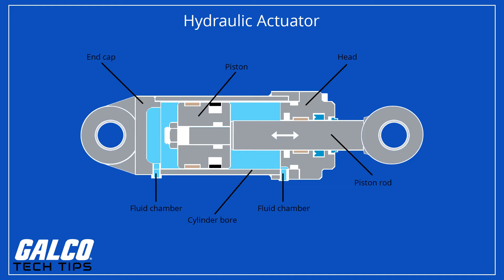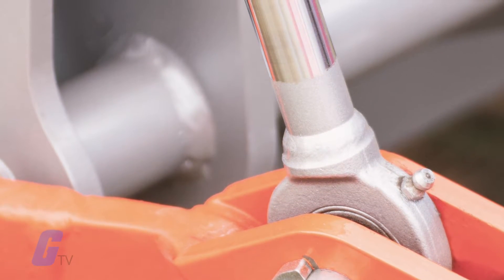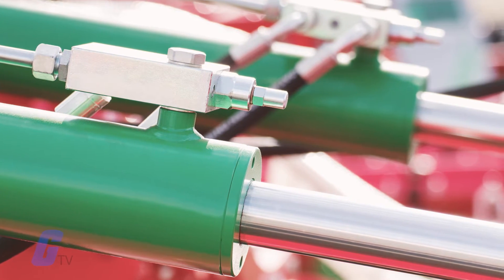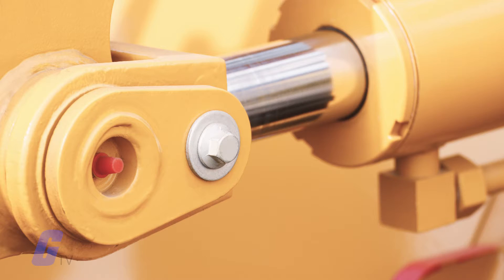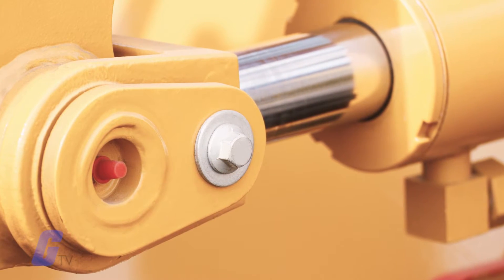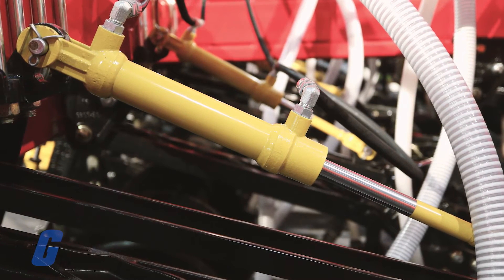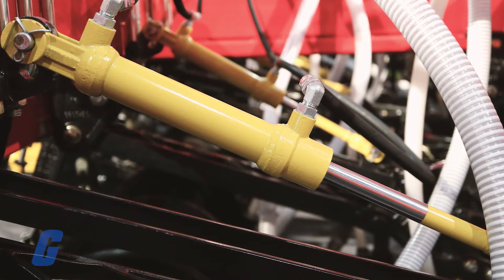The mechanical motion gives an output in terms of linear, rotary, or oscillatory motion. Hydraulic actuators are rugged and suited for high force applications. They can produce forces up to 25 times greater than pneumatic cylinders of equal size, and also operate at pressures as high as 4,000 psi. They can hold force and torque constant without the pump supplying more fluid or pressure, due to the incompressibility of fluids.